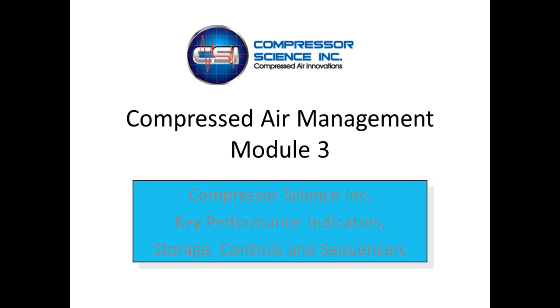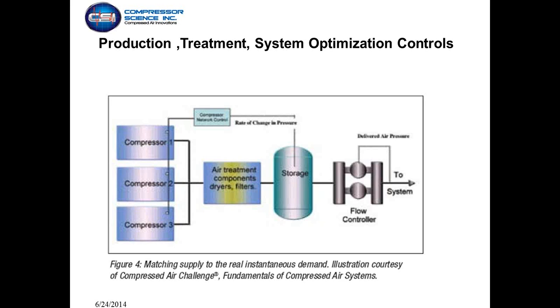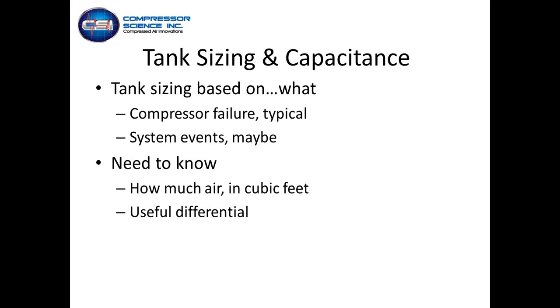Just going to go through briefly before we finish up here: storage, control, and sequencers. Production, treatment system, and optimization controls. In a well-designed system, you're generally going to see the compressors, air treatment, receiver storage where it's feasible or plausible, a flow control valve to regulate pressure into the plant, and then a compressor network control to load and unload the compressors off of one common transducer signal, which is generally in dry storage. That way you're trying to match the supply to the actual demand, providing you resolve the demand issues out in the plant.